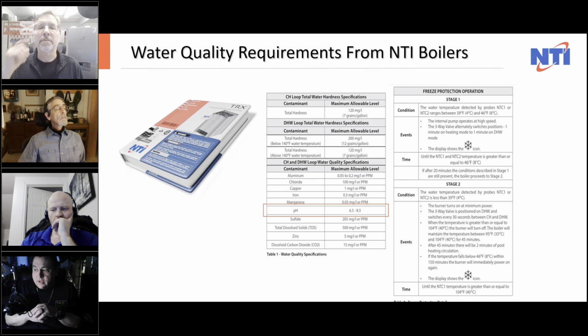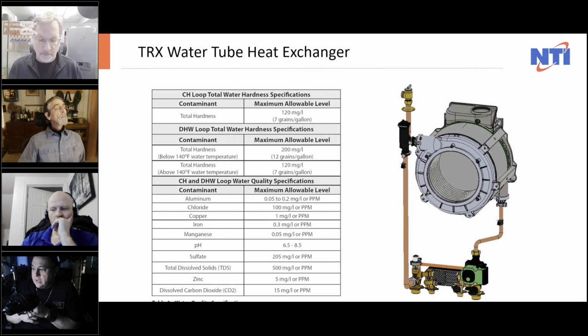So it outlines exactly what we've always said in the manual. Depending on which boiler you're working with, like our smaller TRX series, your pH is going to be 6.5 to 8.5. But then when you jump into the bigger units, like the fire tube, you'll see a little different pH levels. But pH isn't the only thing we need to look at.